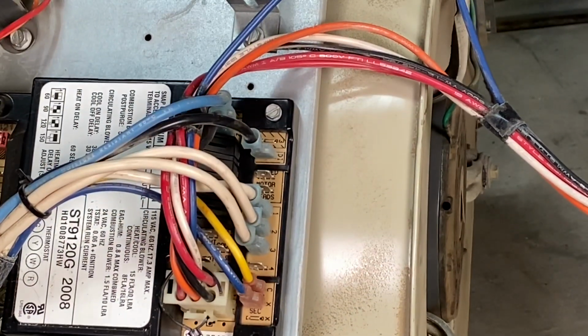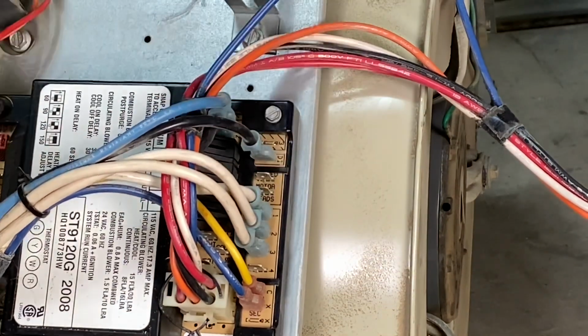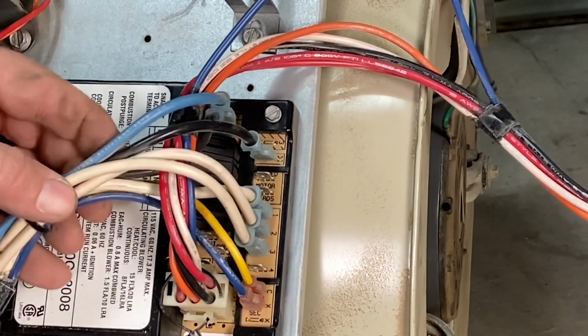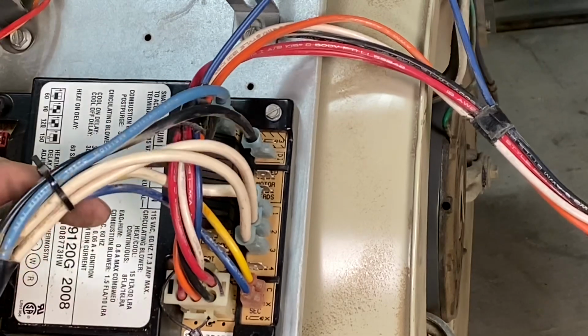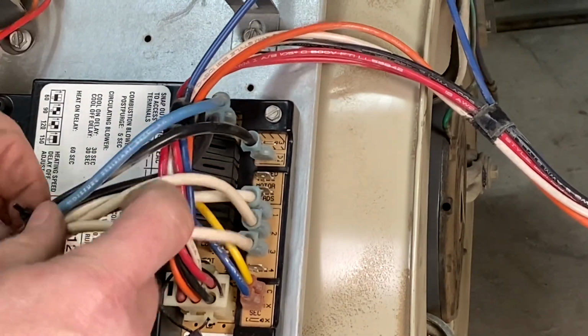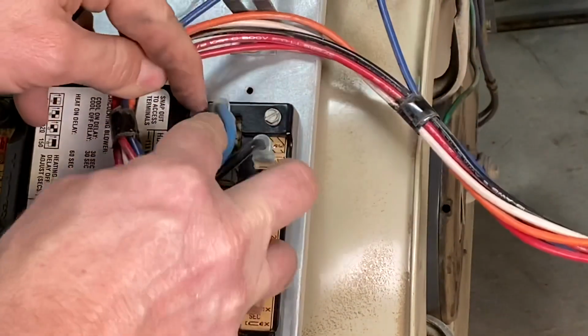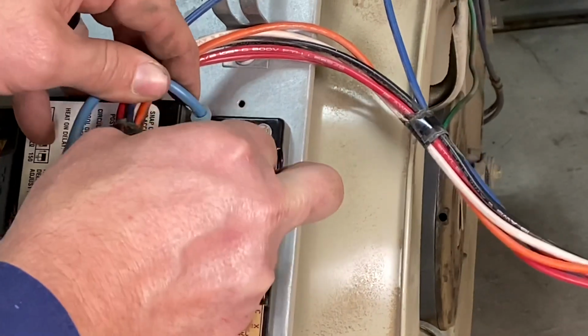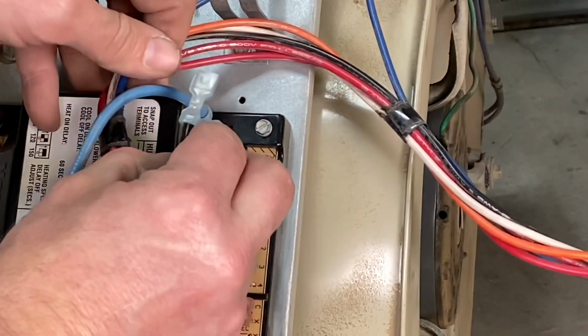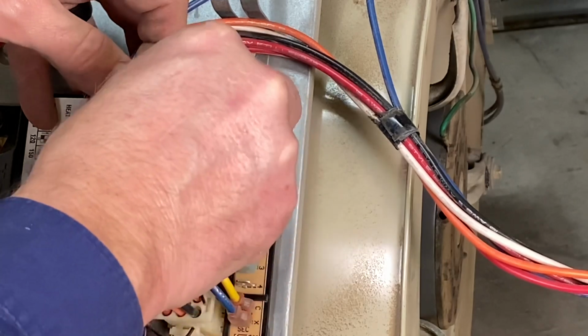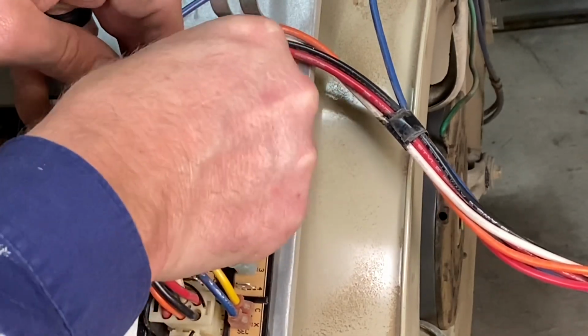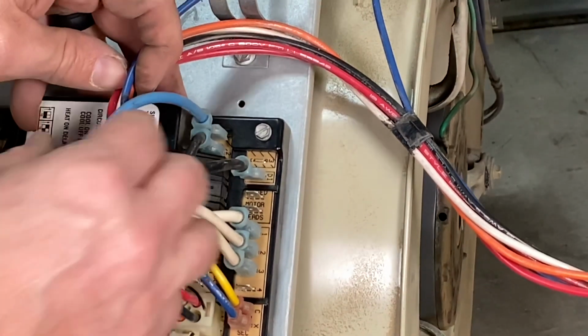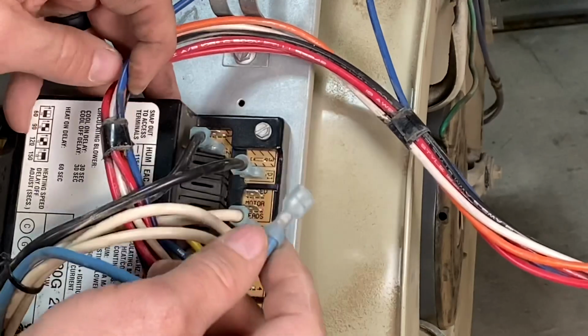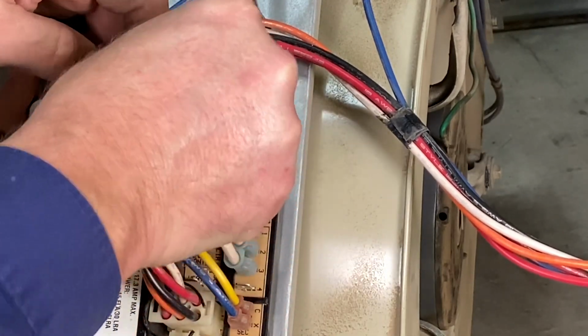The neutral wires for our transformer will be over here, and the hot wire, the black wire for a transformer, if we follow this wire, physically push and follow it, it goes over here on the very top side, and it's just marked terminal number 2, so it doesn't give us any specification of exactly what it's doing or the purpose it's there. This blue wire is coming from our door safety switch, and that's also our main power wire.